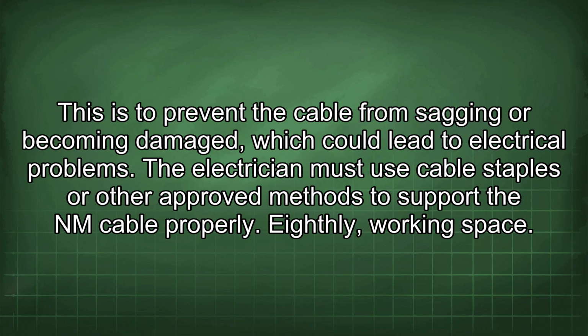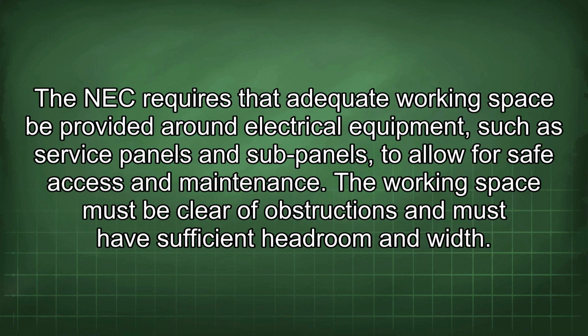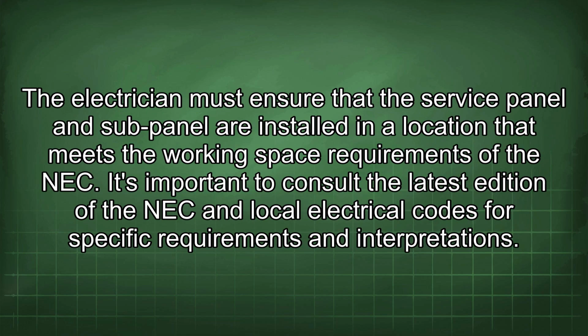Eighthly, working space. The NEC requires that adequate working space be provided around electrical equipment such as service panels and sub-panels to allow for safe access and maintenance. The working space must be clear of obstructions and must have sufficient headroom and width. The electrician must ensure that the service panel and sub-panel are installed in a location that meets the working space requirements of the NEC.